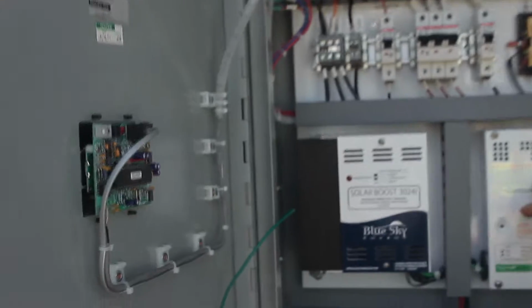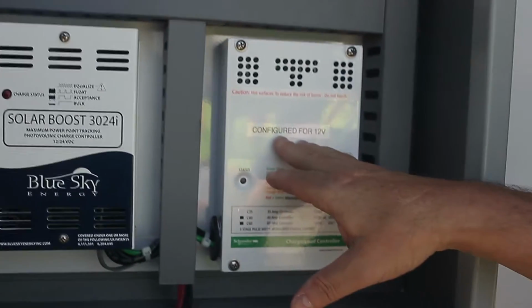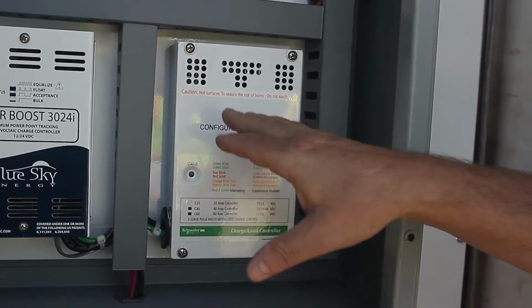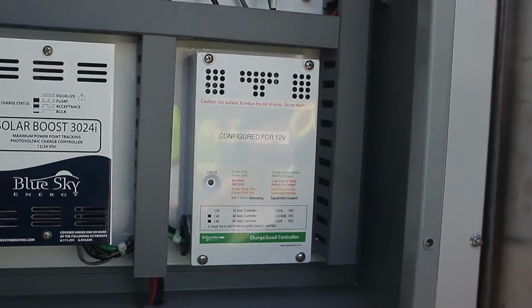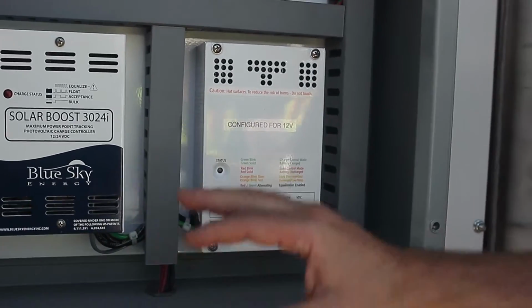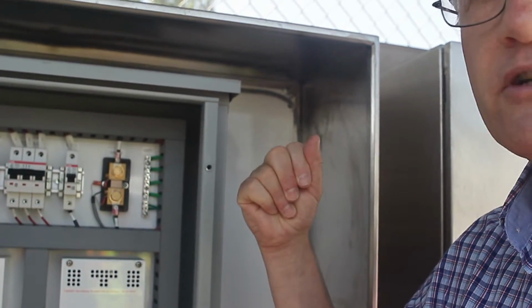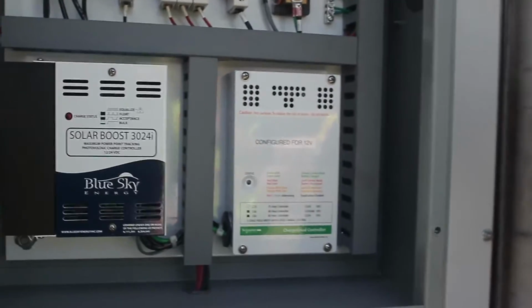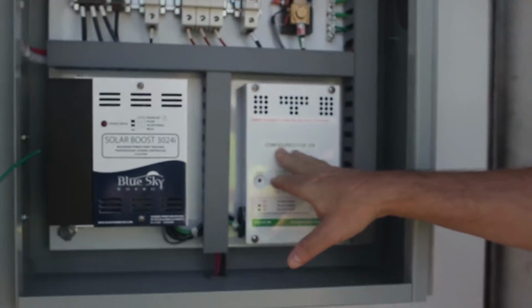The other device here in the box is simply a low voltage disconnect. If the power is reduced such that the batteries get below about 11.5 volts, this will disconnect the batteries and save the batteries so they don't get damaged if there's a problem. So that's the only purpose of this equipment here.